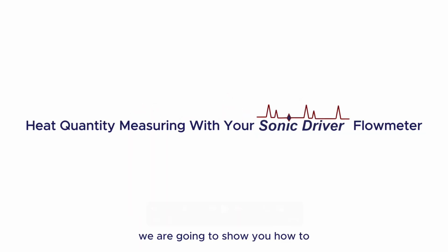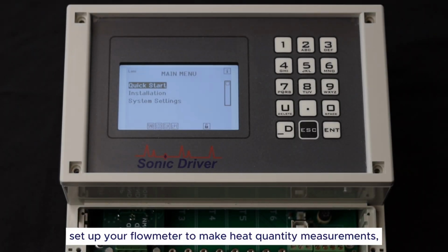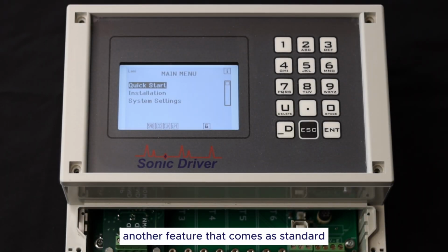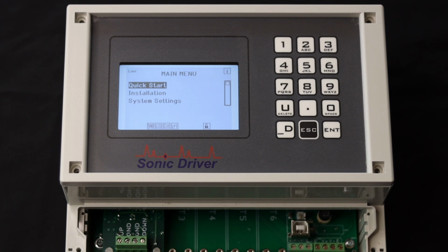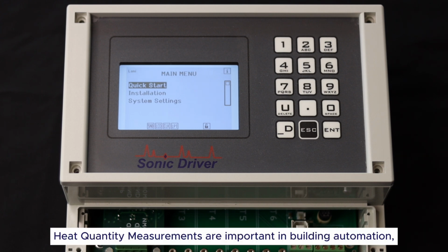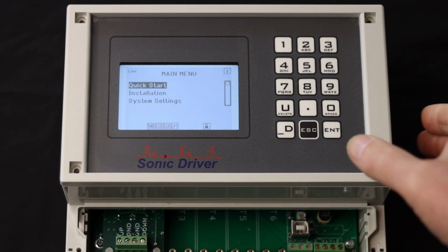In this video, we're going to show you how to set up your Flowmeter to make heat quantity measurements, another feature that comes as standard with your Sonic Driver fixed Flowmeter. Heat quantity measurements are important in building automation when measurements on cooling and heating systems are made.